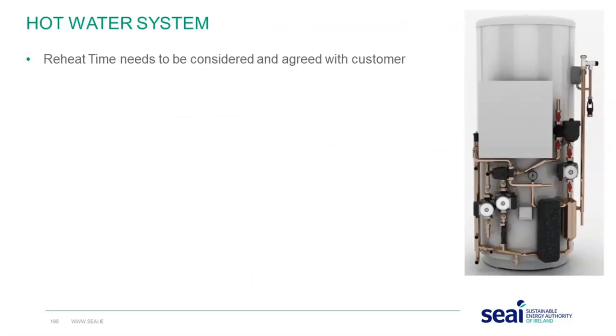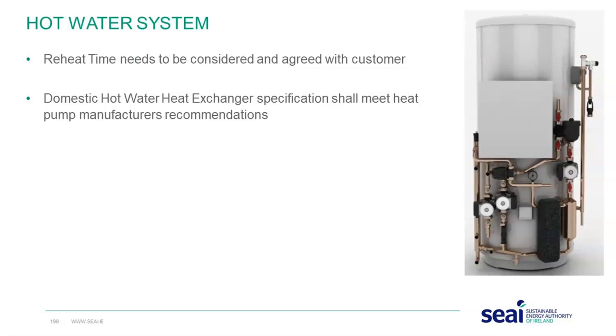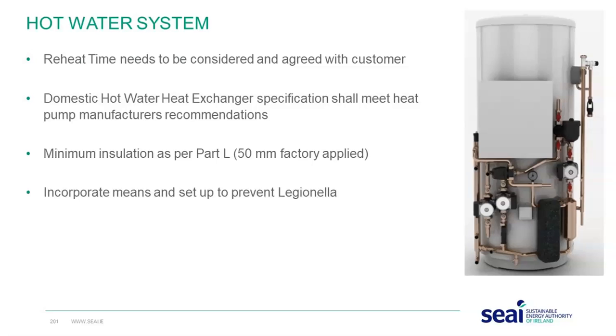Now I bring it to the hot water system. When we're looking at the hot water system, reheat times need to be considered, and you should agree them with the customer. The domestic hot water heat exchanger specification shall meet the heat pump manufacturer's recommendations. From our inspections, what we would find most times is that the indoor and outdoor unit, or the cylinder, is from the same manufacturer and they were both supplied together. But if the cylinder is different from the heat pump, please ensure that the cylinder is capable of meeting the manufacturer's recommendations: length, rate of exchange, size of coil, etc. The minimum insulation of the cylinder must be Part L compliant, for example 50 millimeters factory insulation. There must be some means to prevent Legionella. And the efficiency must be calculated in accordance with EN 16147 at 55 degrees Celsius.